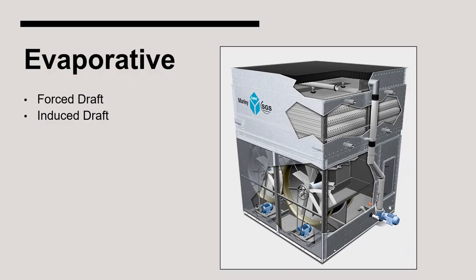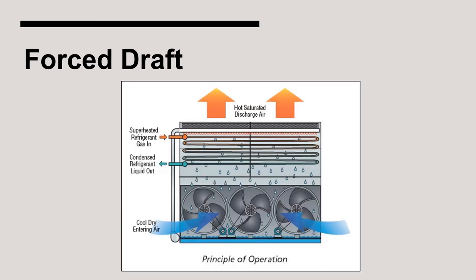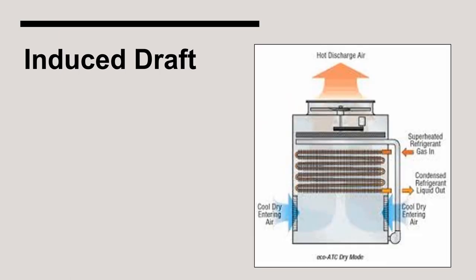The two configurations of evaporative condensers are forced draft and induced draft. The forced draft style of condenser involves fans which push the outside air through the condenser where it flows across the tube bundle and through the mist eliminators at the top of the unit. The fans for induced draft styles of condensers are typically located at the top of the unit. The fans pull outside air through the bottom of the condenser where it flows across the tube bundle. The air exits the condenser through the fan at the top.